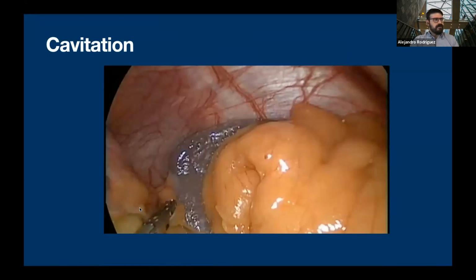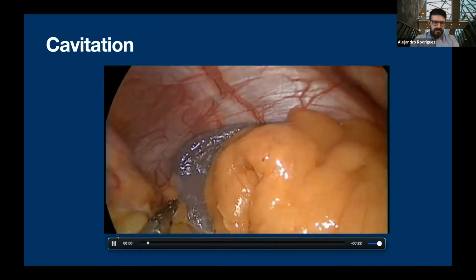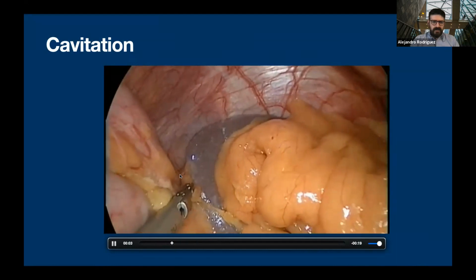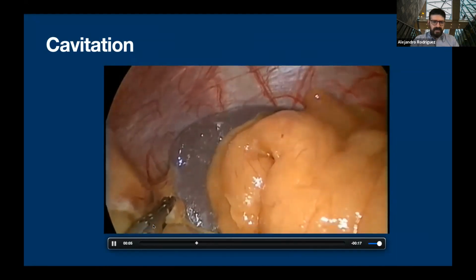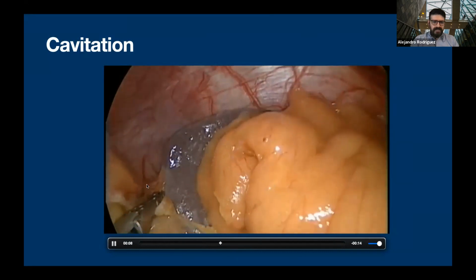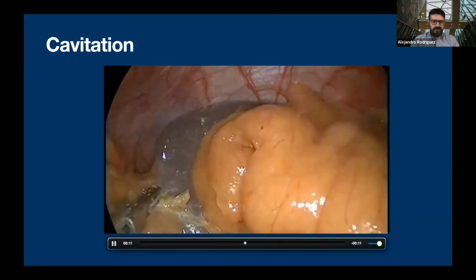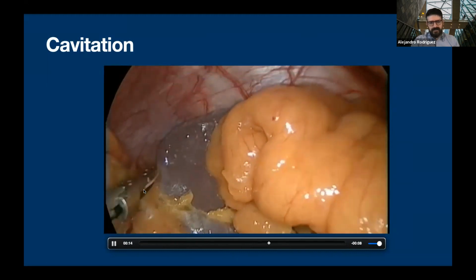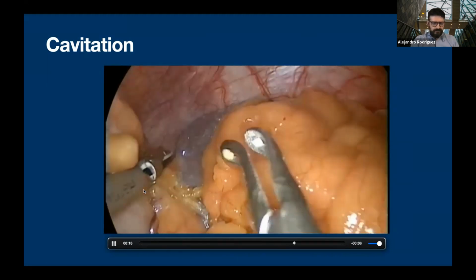This device produces a third effect called cavitation. Essentially this creates a microenvironment where the boiling temperature goes down, so the tissue surrounding it may be expanded by gas produced by tissue evaporation. It's subtle, but you can see here on these last gastric vessels that as the device is activated, cavitation causes this tissue to puff up, which in theory makes dissection a bit easier.